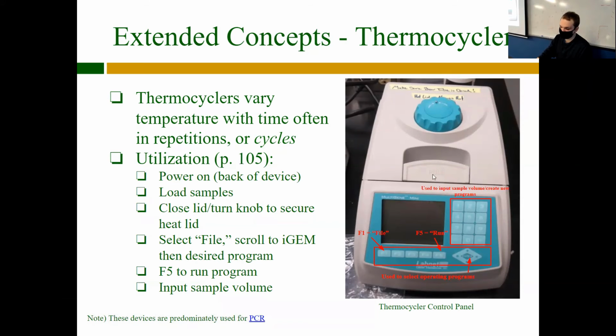Next, you open up this. There's a little pull tab here. You pull it. You load your samples, which are typically going to be microcentrifuge tubes, so very, very tiny epi tubes. They fit into the little slots in there, and then you close the lid and secure it with this nozzle. So this turning knob, what it does is it lowers the heat plate inside the Thermo Cycler so it touches the tube so the tubes can get proper heating. So you want that nice and snug against those tubes.